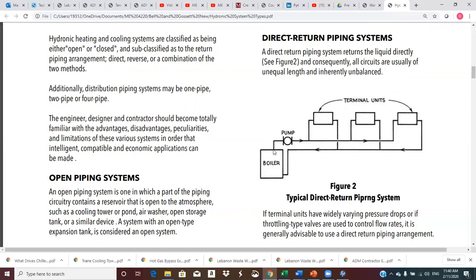If you go, say, from the boiler, all of the 3 circuits have some of this in common from here to here, but then I have a short pipe up to the unit, through the coil, down a short pipe, and the shortest return path. So this is called direct return.